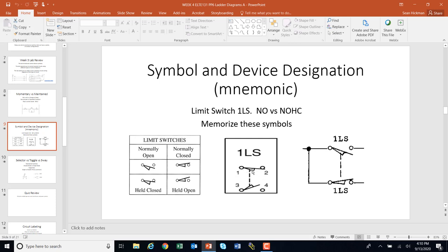Here you have a dashed line between contacts, which means those contacts work together. In this case, this contact is normally open but it's being held closed, and because it's dashed, the other contact is being held open. If you let go, this one would close — it's normally closed — and this one would open — normally open. Here's another example: this is normally closed and this is normally open, but when I hit the limit switch, two sets of contacts change condition — this one closes and this one opens. That's what the dashed line means.